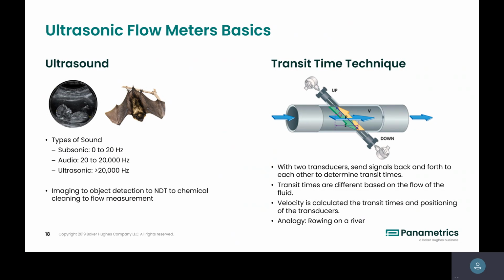It's very simple: two transducers are positioned at about a 45-degree angle, sending a signal back and forth. When the signal travels with the flow, it speeds up; against the flow, it slows down. That timing difference is proportional to the velocity measurement, with the transducers sending signals back and forth.